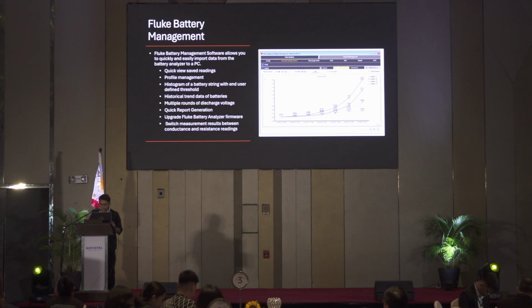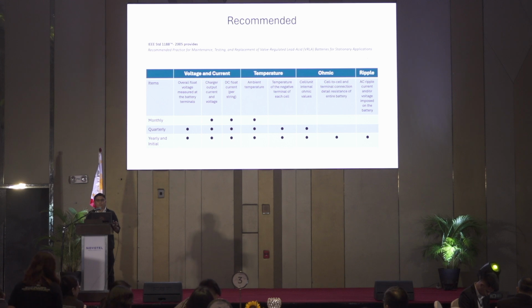According to the IEEE standard 1188, here's the recommended practice for battery maintenance. For voltage and current, checks could be quarterly or yearly. For temperature, yearly, and also ohmic and ripple checks. This standard is your guide on how to maintain the battery.